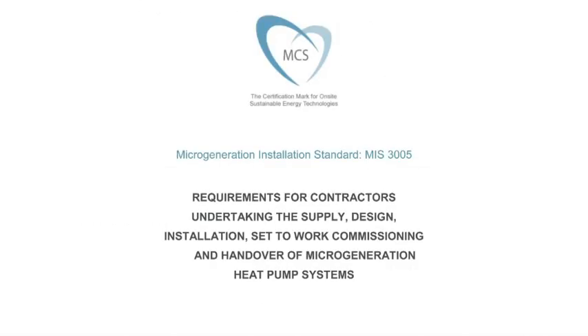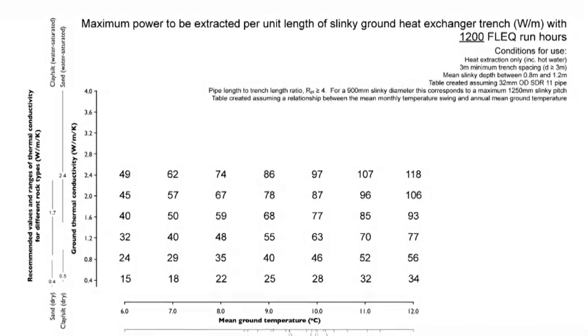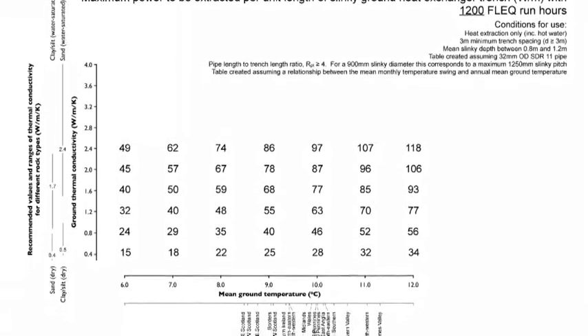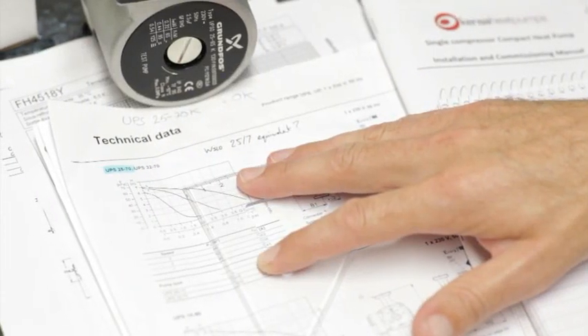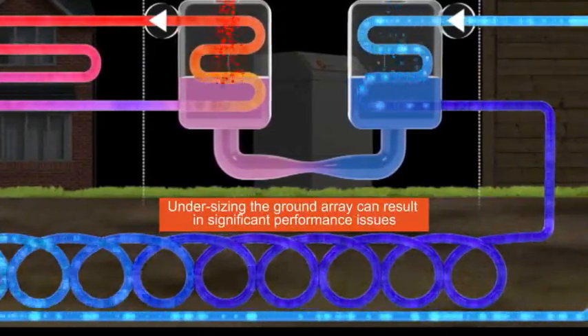Based upon these criteria, the latest MCS MIS 3005 installer standard utilises lookup tables to establish ground array designs. These tables are an extension of the methodology successfully employed by Kensa since 1999 and provide a simple to use, conservative design. Kensa's designers and expert third parties also have the opportunity to use sophisticated software for more complex projects, but these lookup tables are well suited for typical residential projects. Kensa has developed a design wizard which automatically generates an MCS approved ground array design and quote once the relevant project details have been entered.